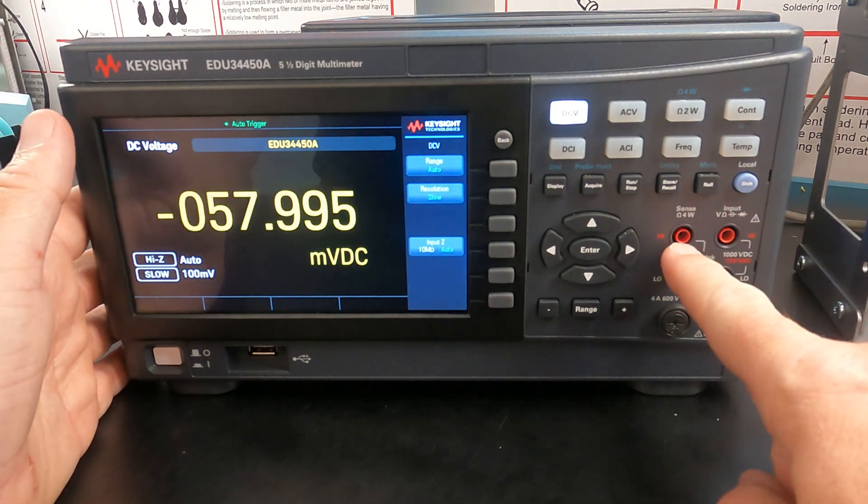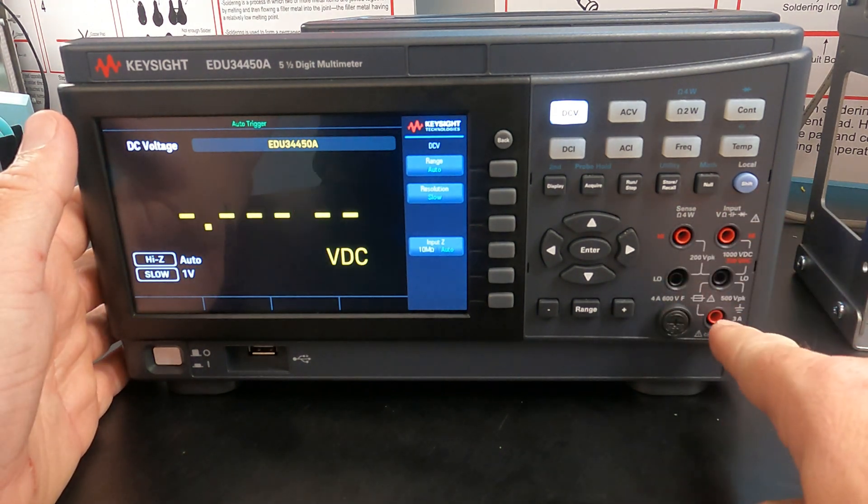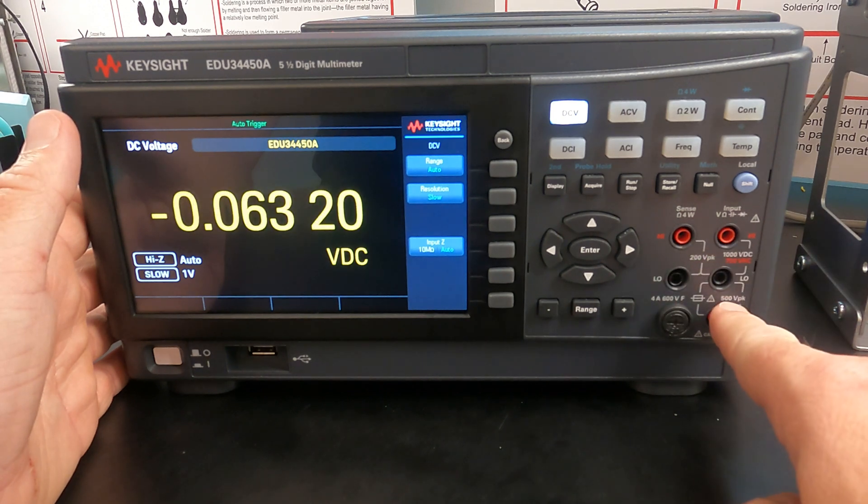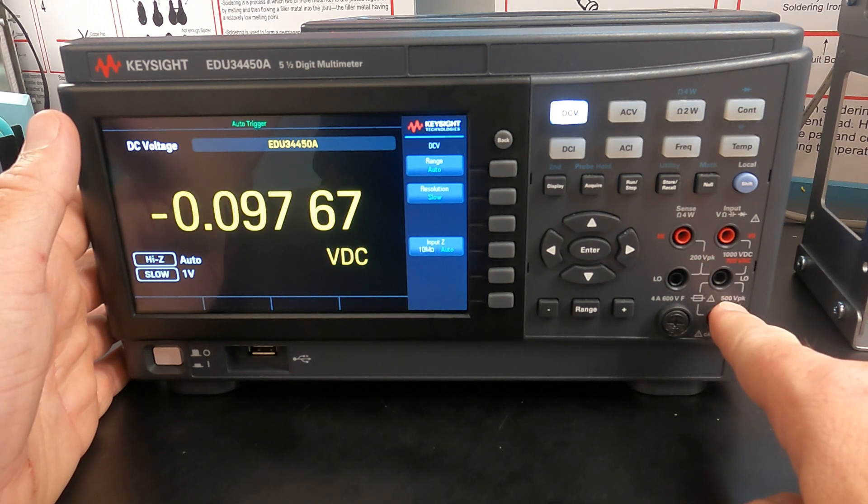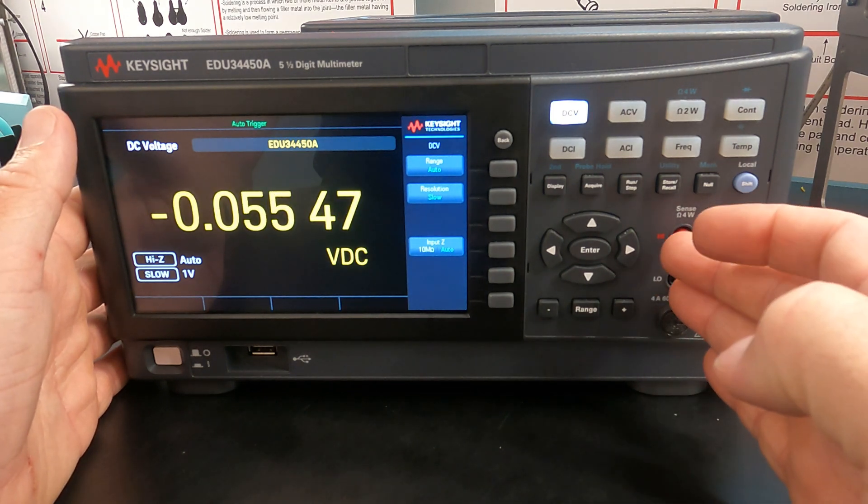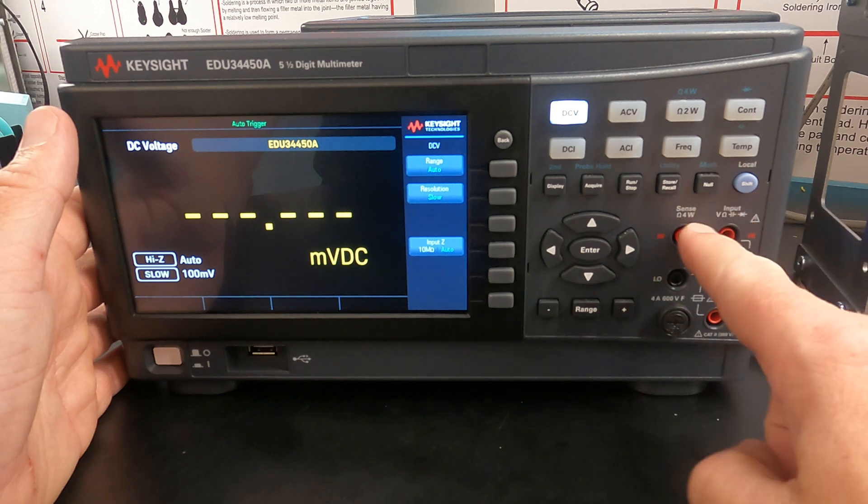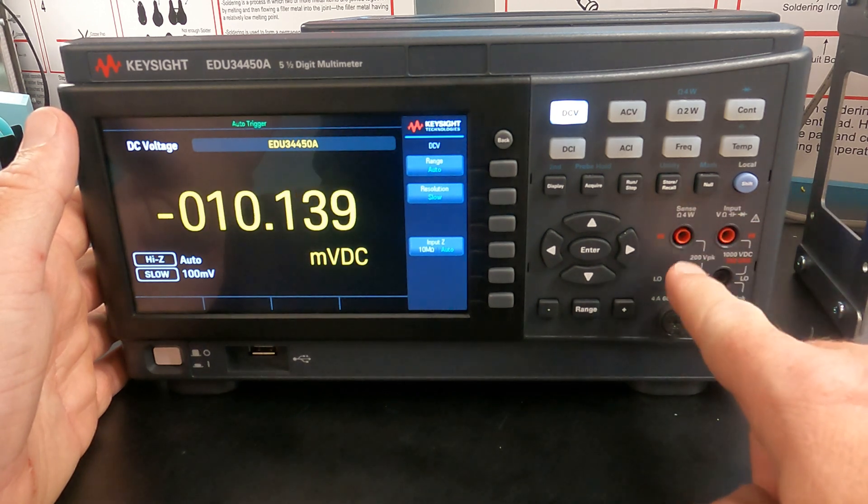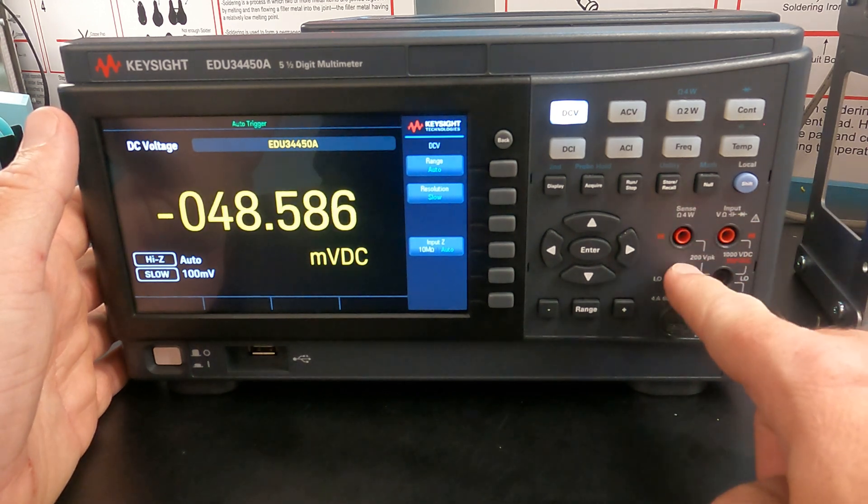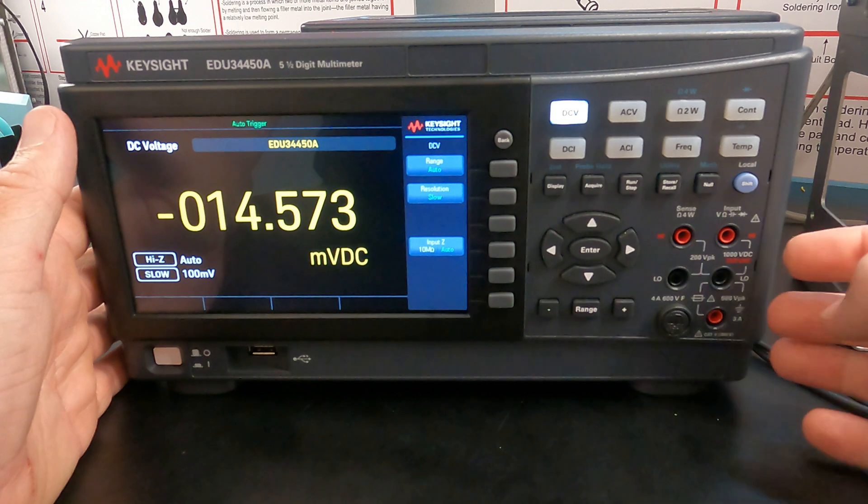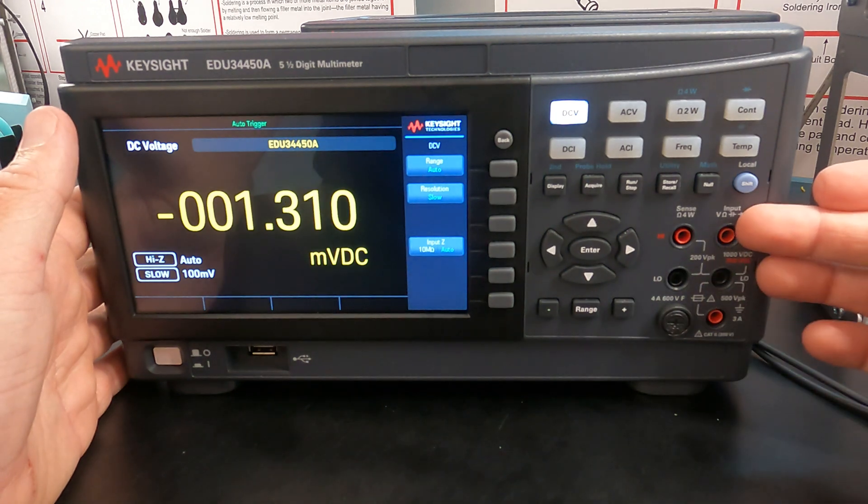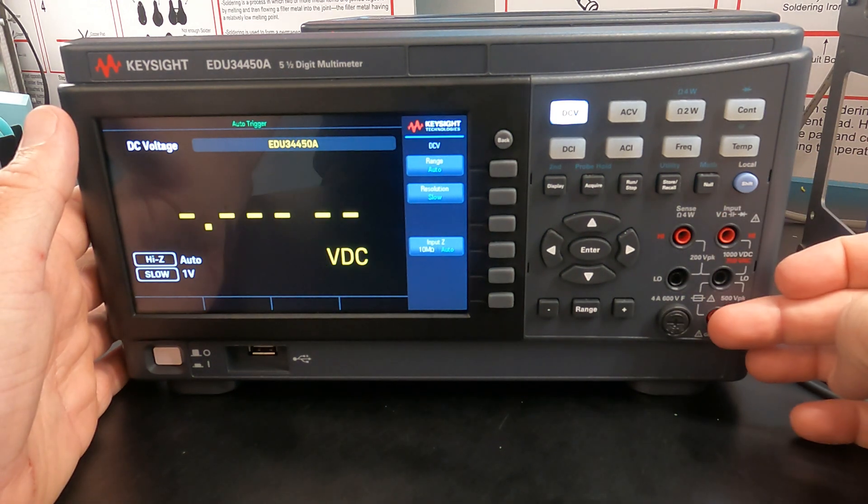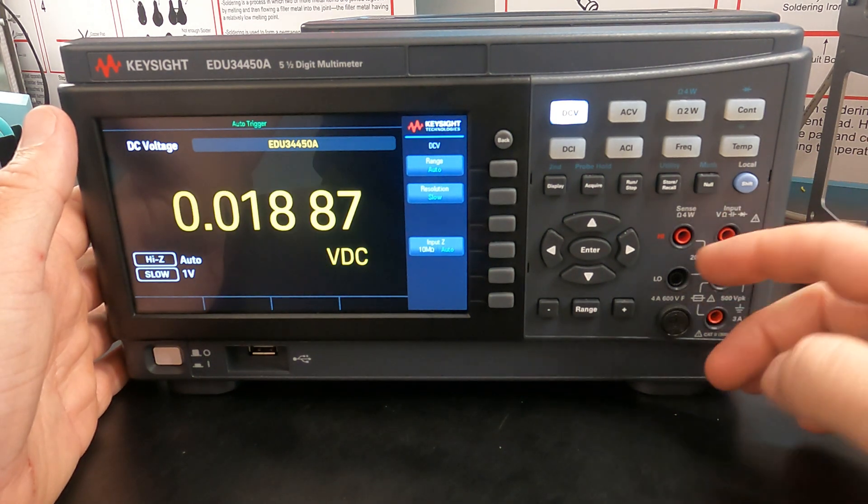So over here we have five inputs. Now, typically, unless you are making what we call four wire measurements, you do not want to use the two inputs on the left. You only want to use these three inputs on the right for most measurements.